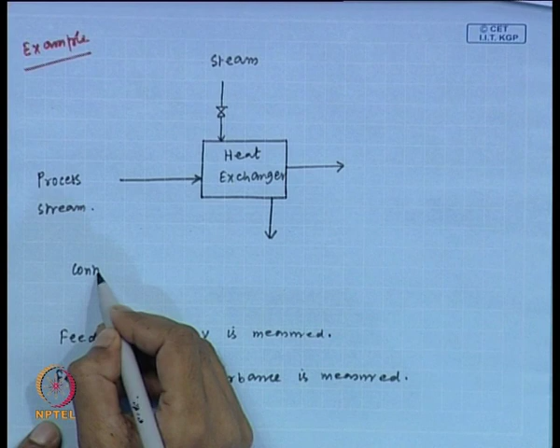Fine. Now, for this heat exchanger, our control objective is to maintain the temperature of the process stream. Our control objective is to maintain the temperature at its set point. What is the manipulated variable? Manipulated variable is steam flow rate. This is the manipulated variable. What are the disturbances? One is process stream flow rate, another one is process stream temperature Ti. So, flow rate and temperature Ti, these two are the disturbance variables.